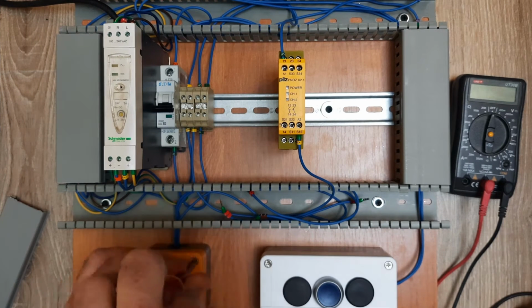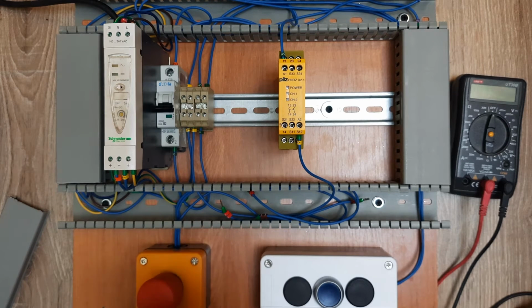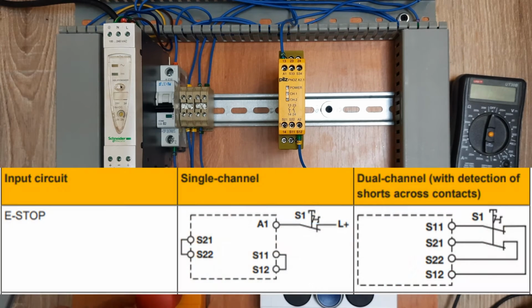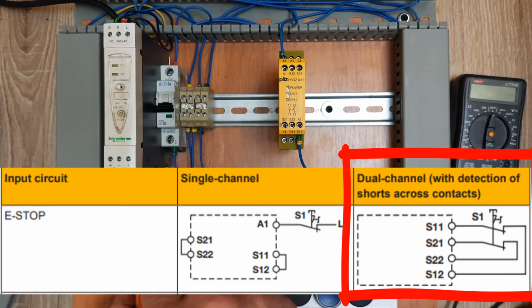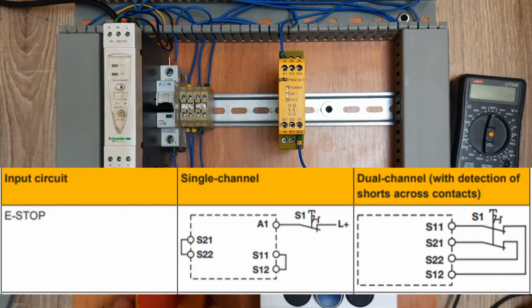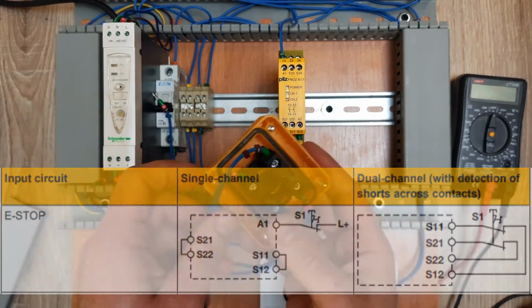Now it's time to start connecting safety inputs. As you can see in the manual, we've got two options. We're going to use option number 2, which is dual channel operational mode. The e-stop button is equipped with two normally closed contacts. One contact is connected between terminals S11 and S12. The second contact is connected to terminals S21 and S22.